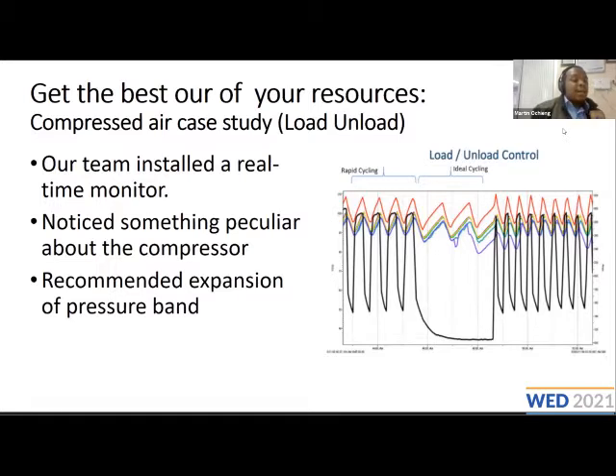So for one of our clients during an energy audit, our team was able to install a real-time energy monitor. And from the monitoring data that we're getting, we noticed something peculiar about the compressor. Basically, a normal load and unload compressor should be operating in this particular section here, within the ideal load cycling here.